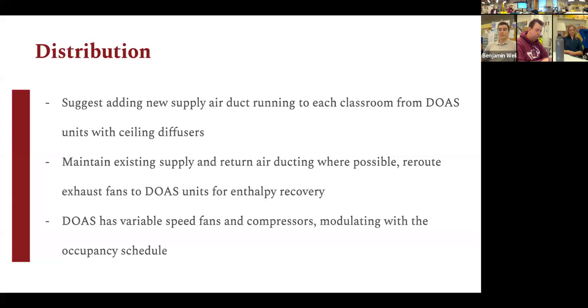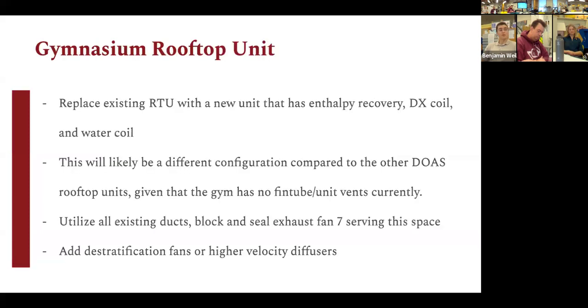But in those spaces that have the exhaust fans, we're able to reuse that return ductwork. And instead of having that air get directly exhausted through the exhaust fans in the roof, we propose just adding runs of return duct to go up to those rooftop units so that we can, as pictured before, use enthalpy recovery where those two air streams cross each other, and then you get better efficiency for your ventilation. Oh yeah, and the DOAS units also have variable speed fans and compressors.